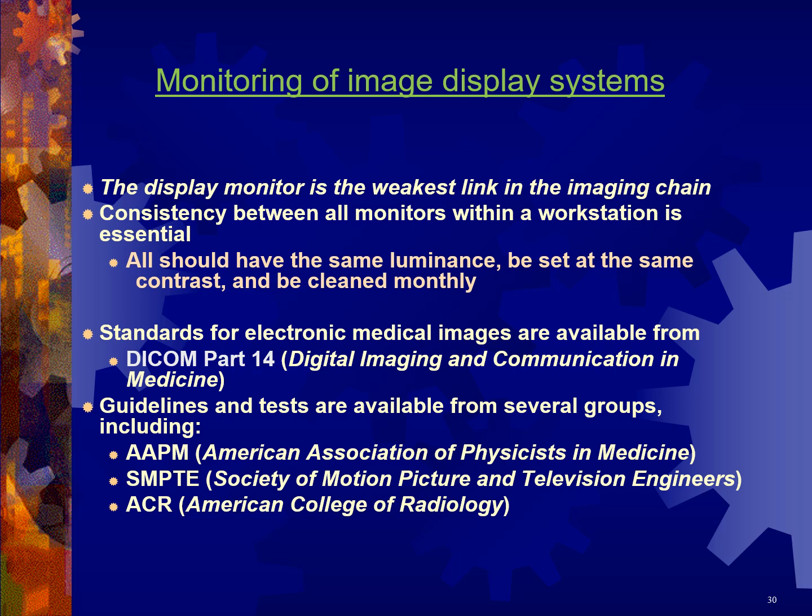The monitors have to meet the specs for DICOM Part 14. So if you're displaying medical images on a monitor, the contrast and brightness should be set to match the levels recommended by DICOM Part 14, and no one should be messing with the brightness and contrast of the monitor after it has been calibrated and set.